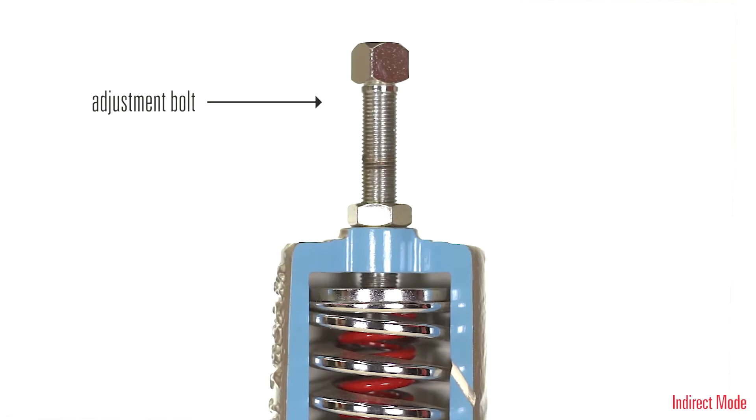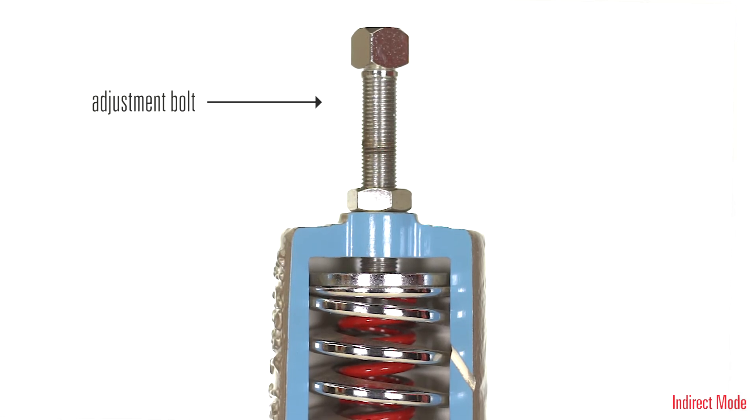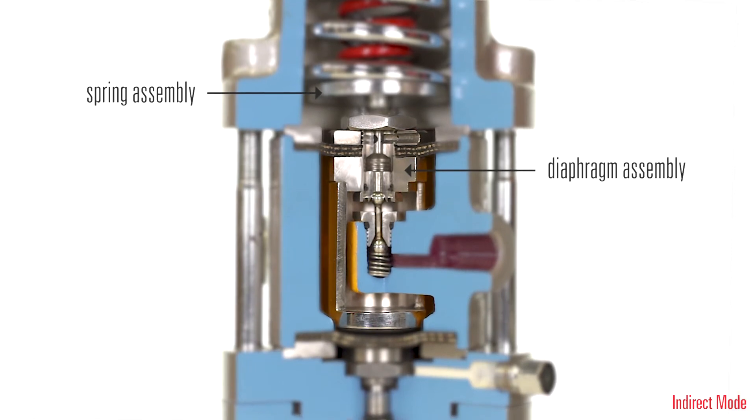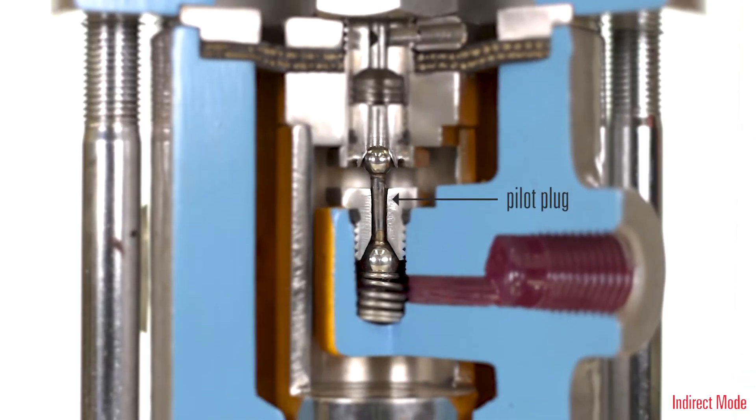The adjustment bolt on top is used to create the set point. As it is tightened, the spring assembly presses down on the diaphragm assembly and positions the pilot plug.